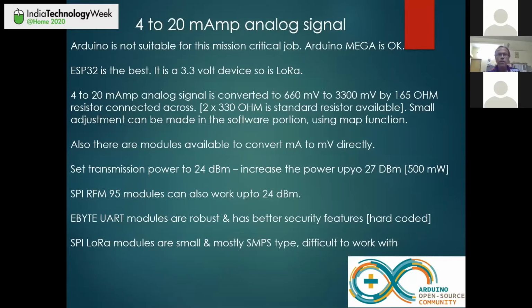Here is the problem we faced: our machine could take analog signal in the form of voltage, whereas the machine was providing 4 to 20 milliampere analog signal. There are small boards available which simply transfer your 4 to 20 milliampere into a voltage level, any voltage setup like 0 to 3.3, 0 to 5, or 0 to 10.